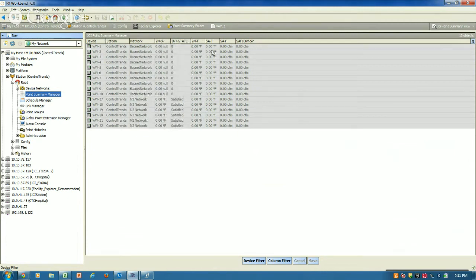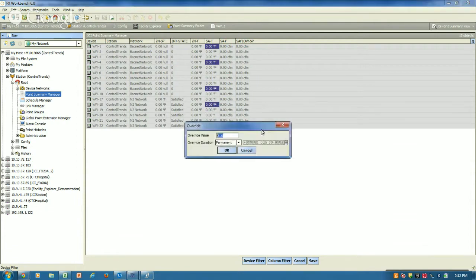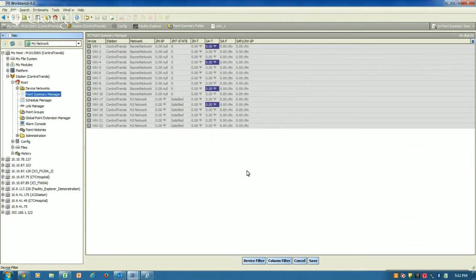Most importantly, you can take a point and override it—either one point, or by holding down shift or control and right-clicking, override all of them at once. So now I have a global override for all those points. For example, if this column is something like heating valve output or damper output, you could override everything to 100% for whatever period of time.